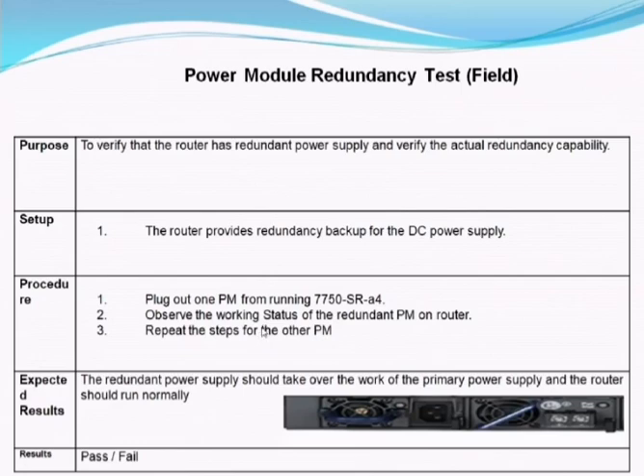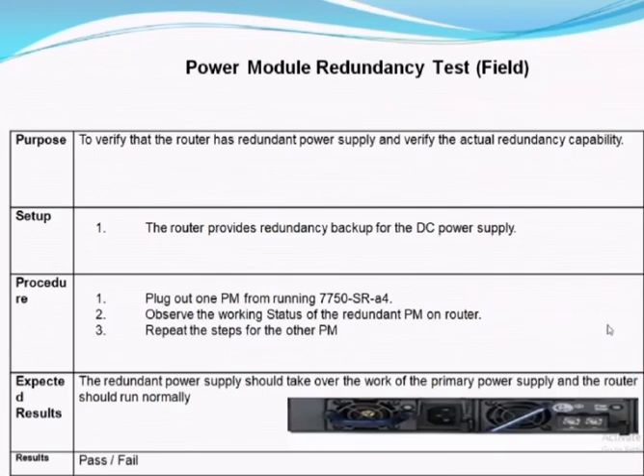One by one we plug out the power supply units. First we plug out the main power supply, check its working status, then insert it back and check whether it is running normally. The same procedure is done for the backup power supply. If expected results show the power supply is running normally, the test is passed; otherwise it fails.